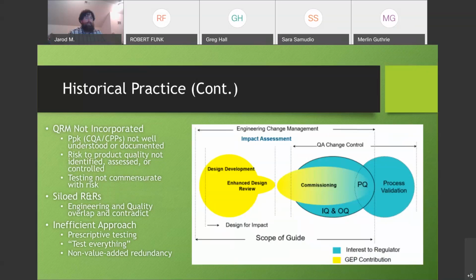Again, it was an everything-gets-tested kind of practice. You had to verify every single line item of a requirement, because if it's a requirement, then it's important - irrespective of its impact to product quality, to patient safety, and also in not only its functional application, but also in the individuals executing the commissioning and qualification activities.